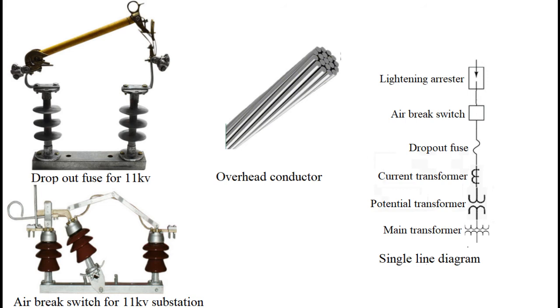This switch shall be outside the inner area marked by four poles, so that if the air break switch emits some sparks, those will fall outside the inner area where the transformer is planned to be installed. Pin insulators have to be installed at the bottom of the switch so that the conductor will pass through the top of the pin insulator and reach the overhead conductor. After the overhead conductors, pin insulators at the top of the other pair of poles are required to connect the dropout fuses. These dropout fuses shall also be outside the rectangular area formed by the four poles. After the CTPT unit, that may be an independent unit or 3 CTs and 3 PTs as separate units, HT supply is connected to the HT side of the plinth mounted transformer.